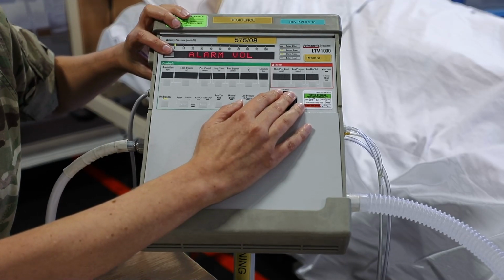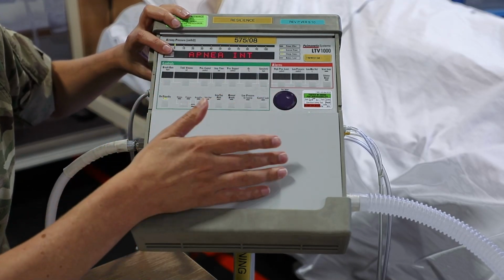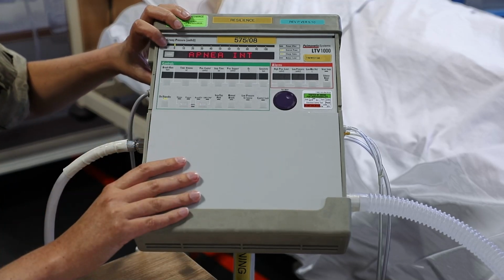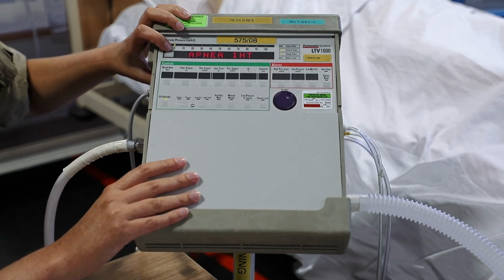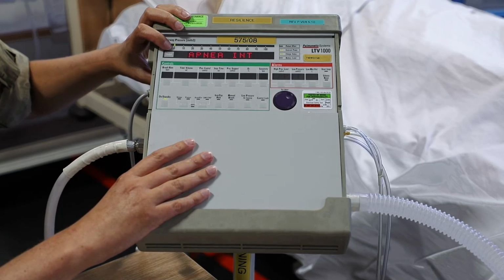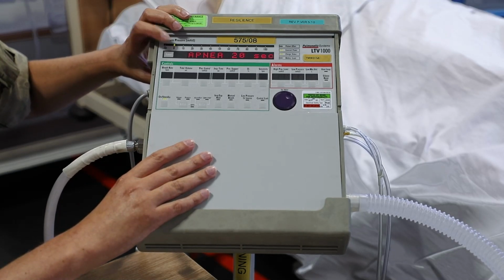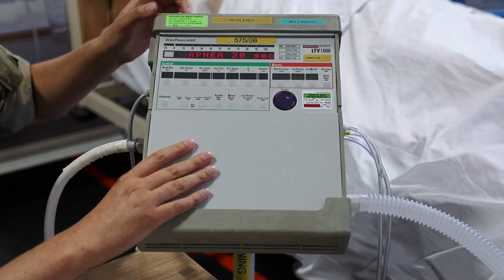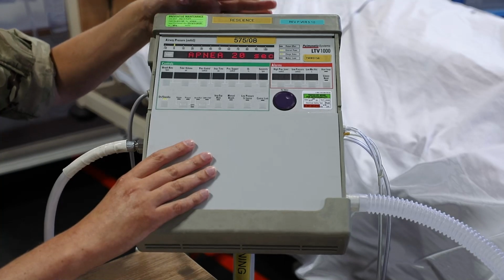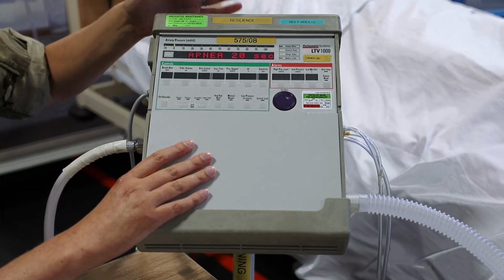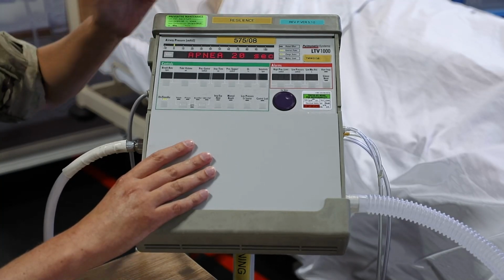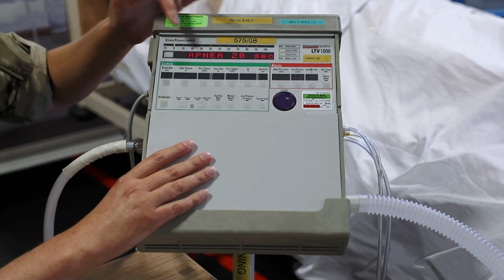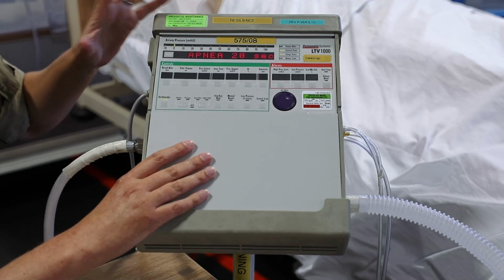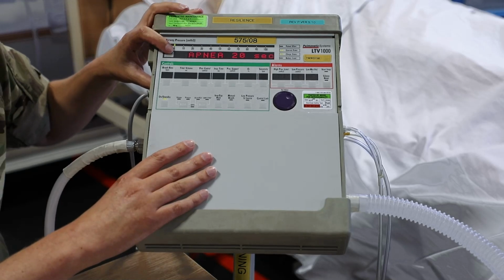This is where you're going to have to turn the dial, because these are menus within menus, so you can get a little bit lost here. But the next option after turning the dial to the right is apnea interval. So if we press select, it gives us a 20-second interval. So the LTV will allow the patient to go apneic for up to 20 seconds before it goes into an apnea backup. You can adjust that, you can go up and down on that, but it's set at 20 as standard.